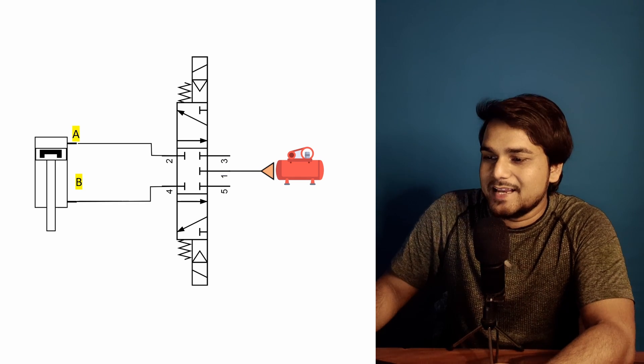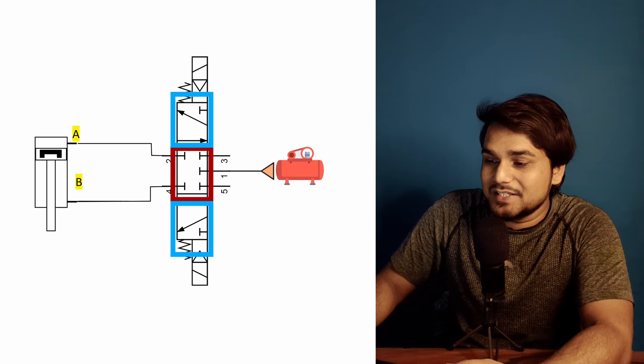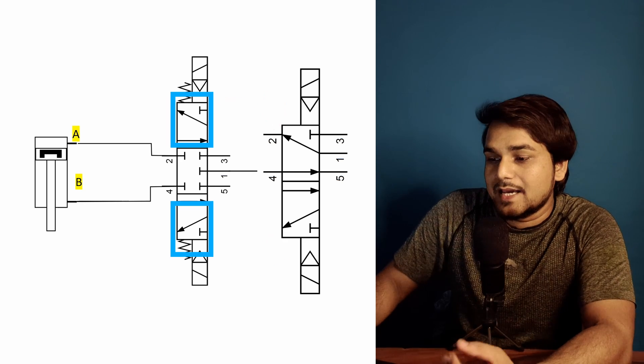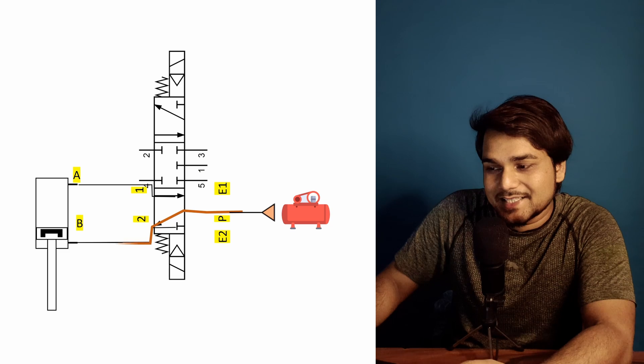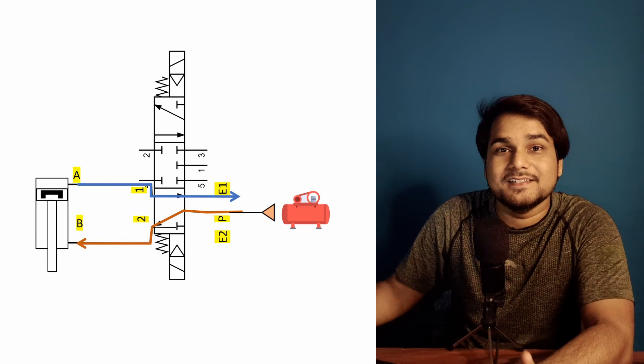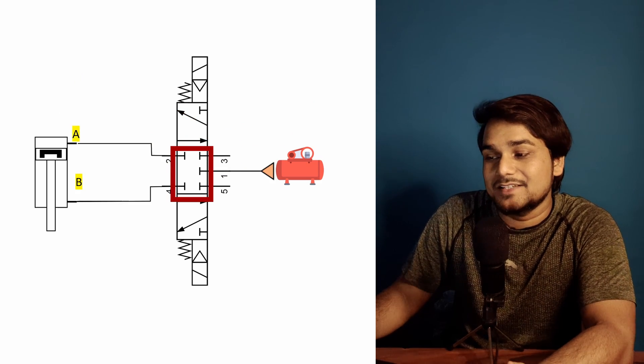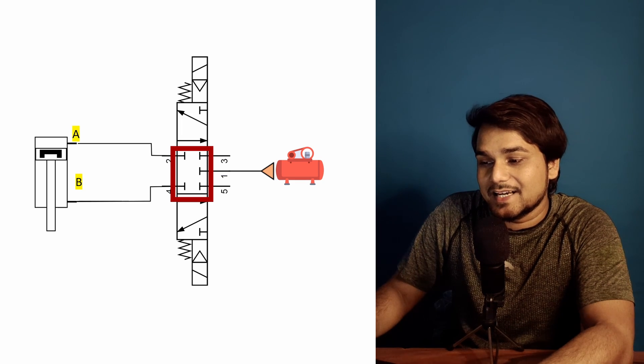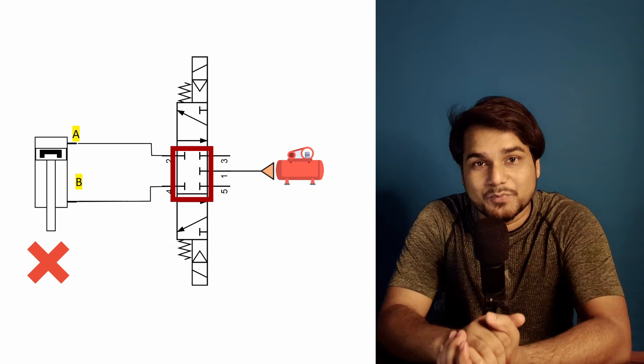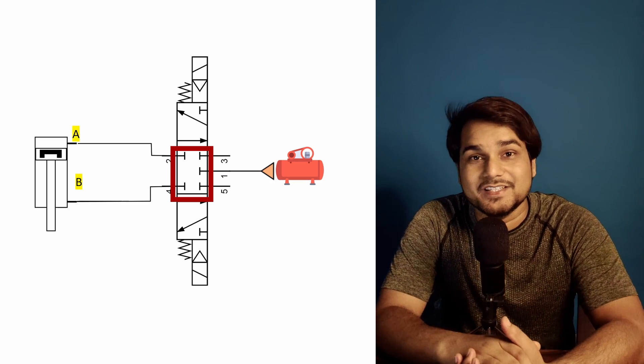The 5/3 center closed valve also has 5 ports and the same connection method, but has 3 position states. The two outer position states operate the pneumatic cylinder up and down exactly as the 5/2 valve does. The middle position state closes the compressed air supply and also closes the pneumatic cylinder connection ports, so the cylinder stops and won't move. By default the 5/3 center closed valve sits in the center closed position state.